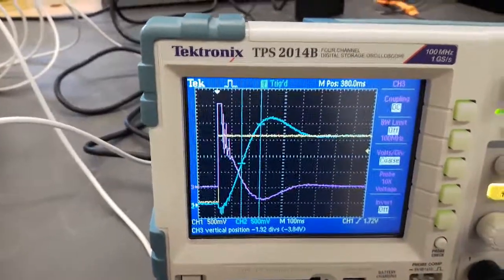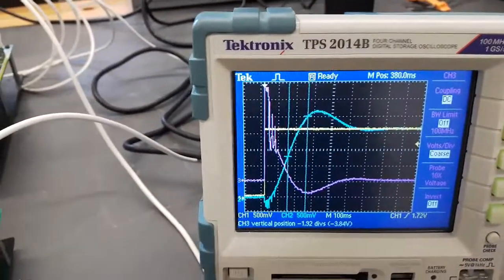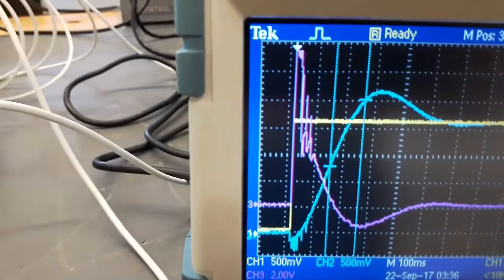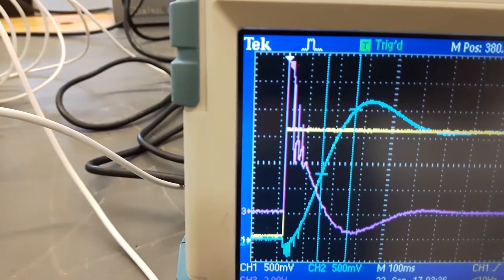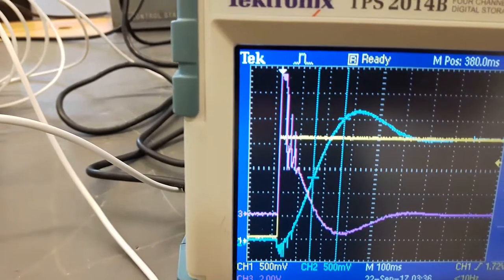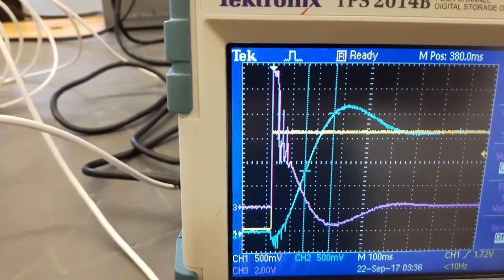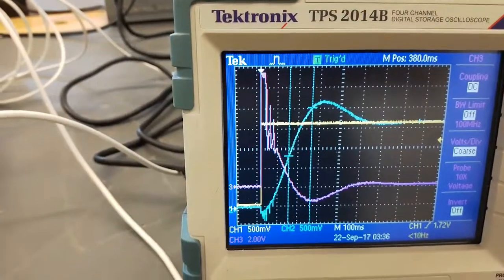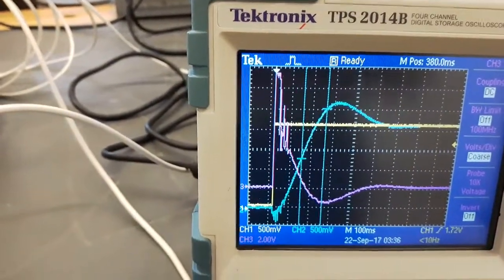So we're sending a hard limit right at the beginning there. So if you see that, that's a hard limit where the arrow is. So it's limited. We've gone, we're into wind-up now. This board doesn't have anti-wind-up. And then we resume out of that.